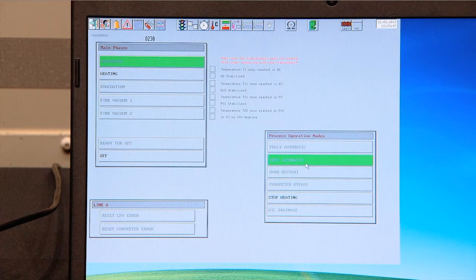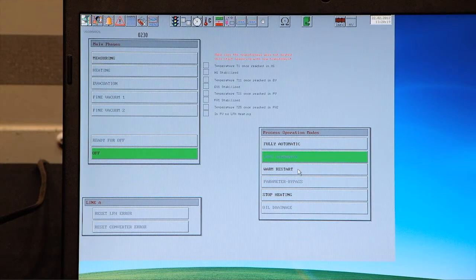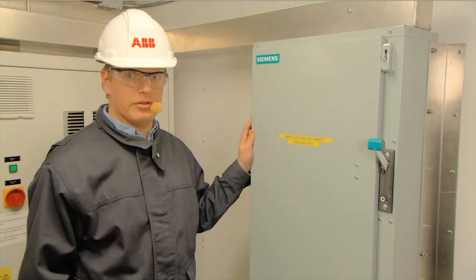That means that the transformer has not been running and is at an ambient temperature, or the previous resistance reference values have been lost and a new measurement needs to be performed. A warm restart bypasses the first stage that correlates the resistance of the windings with their temperatures. It goes directly to the heating stage.